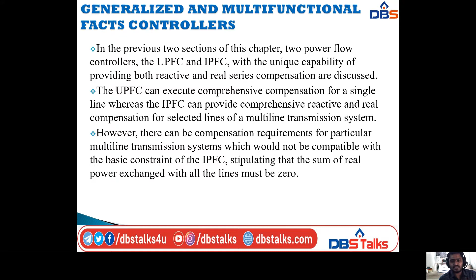However, there can be compensation requirements for particular multi-line transmission systems which would not be compatible with the basic constraint of the IPFC, stipulating that the sum of real power exchanged with all the lines must be 0. This constraint could be particularly restrictive under an emergency contingency, when those lines which were to support the prime lines would also be overloaded.